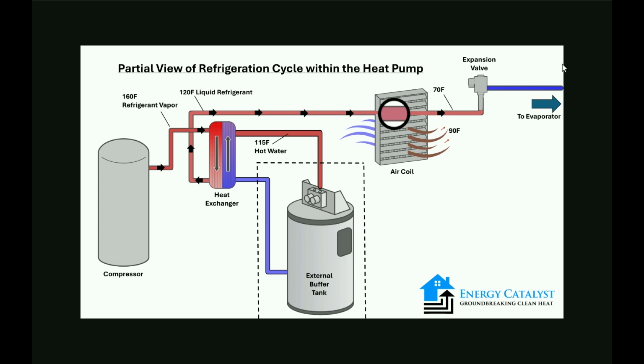Perfect. But then downstream of that, if you follow it, it goes to the expansion valve, right? And if you left it that way, what you would see is that the expansion valve's job is to basically absorb heat. On the other side of that expansion valve, it's kind of like a freezer. It's there to cool things down.